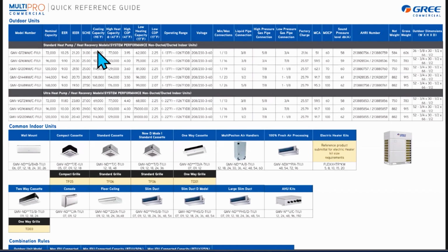One thing I was talking with Greg about earlier - notice on the IEER, on that 6-ton unit, it's 21.2, but in the simultaneous cooling and heating it's 31. In a heat recovery mode, we get the extra efficiency by reusing or redirecting that heat, as opposed to dispelling it into the atmosphere.